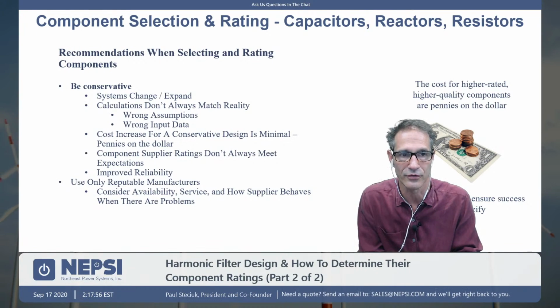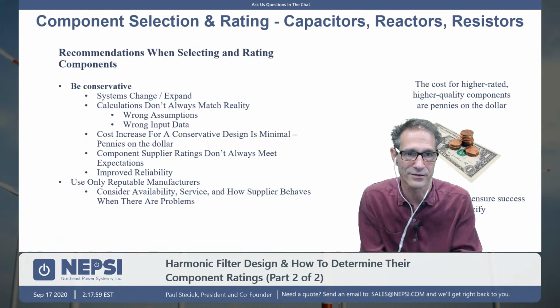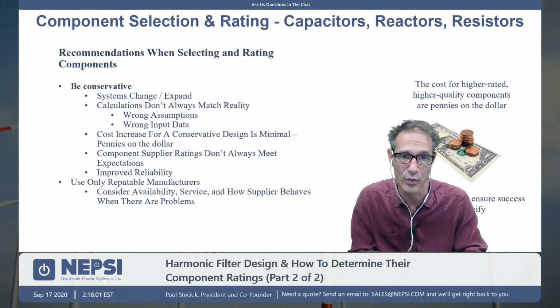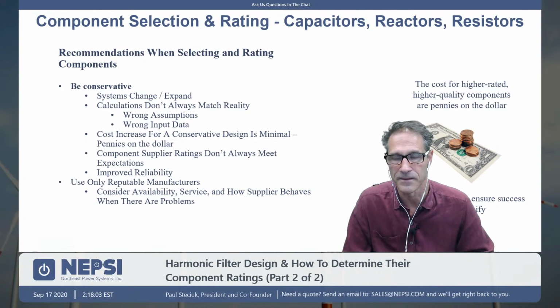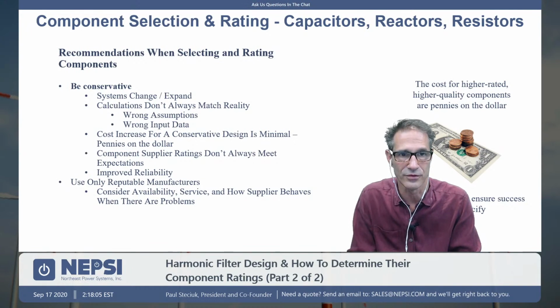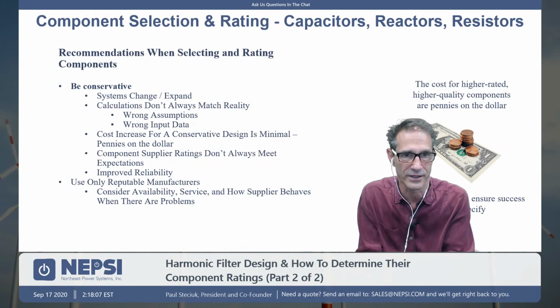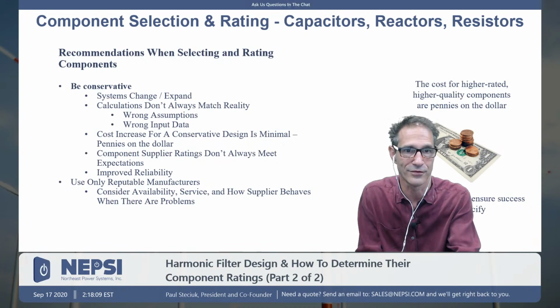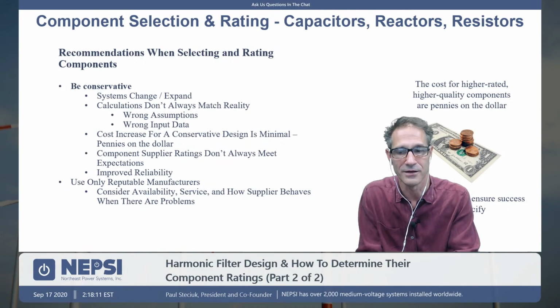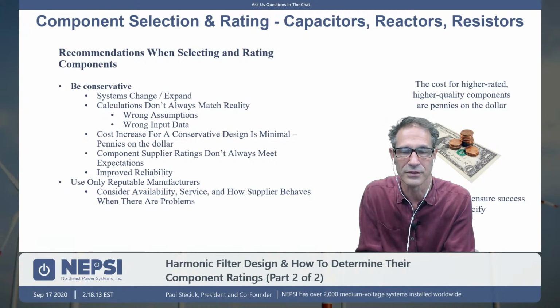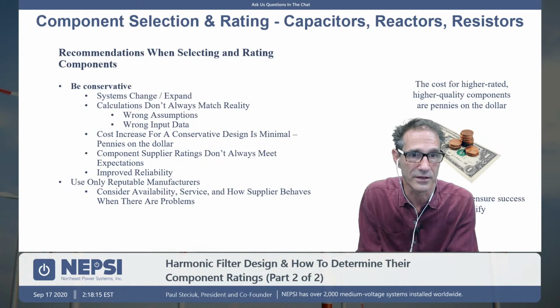So normally you want to be conservative with your design for that reason, because you might actually get more harmonic current flow into your filter. You might stress those components a little bit more. So you want to be very conservative with your design. The other thing to remember is that systems do change. You design a harmonic filter for today. Well, in the future, after the study is long gone and done and the harmonic filter is installed, it could be 5, 6, 7, 10 years later.